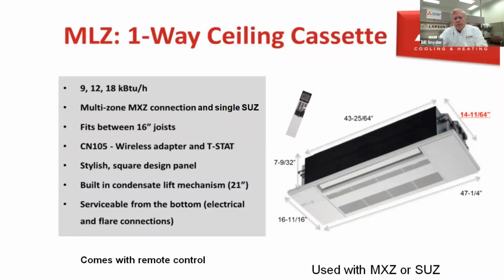Now this is a one-way ceiling cassette. There's one louver on this one. The one I showed you earlier, the 2 foot by 2 foot, had 4 louvers on it. This one only has the one louver. It's only 14 and 11/64 wide, so it fits between 16-inch on-center floor joists or ceiling trusses. So if you had to go up into a ceiling in an attic or something, this would be the one to use. Every serviceable part is serviceable from below. So you don't have to have an access panel to get up into the side of this thing. It's all serviceable from below.